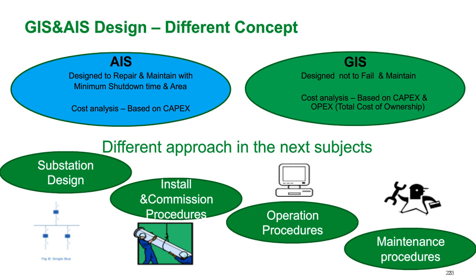Looking at some of our Schneider products, typically the routine maintenance is a visual inspection of the switchgear and an inspection of the mechanism of the circuit breaker outside the gas tank. So you're never exposed to medium voltage. You maintain arc resistance during the maintenance cycle, and this is something that can be done in a matter of minutes rather than a matter of hours. That's what we mean when we say no maintenance. It's no maintenance of the medium voltage circuit.